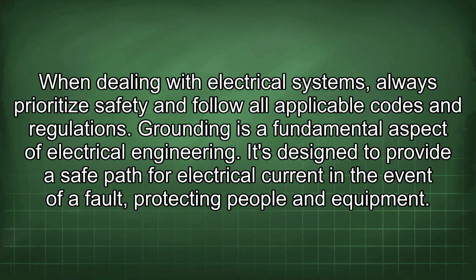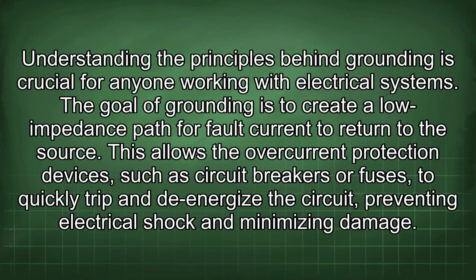Grounding is a fundamental aspect of electrical engineering. It's designed to provide a safe path for electrical current in the event of a fault, protecting people and equipment. Understanding the principles behind grounding is crucial for anyone working with electrical systems. The goal of grounding is to create a lower impedance path for fault current to return to the source. This allows the overcurrent protection devices, such as circuit breakers or fuses, to quickly trip and de-energize the circuit, preventing electrical shock and minimizing damage.